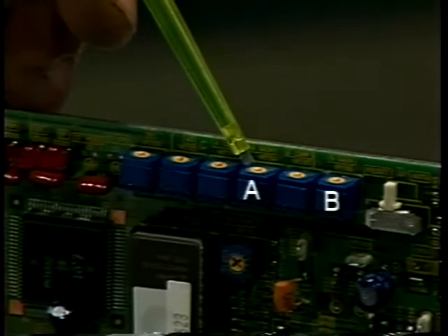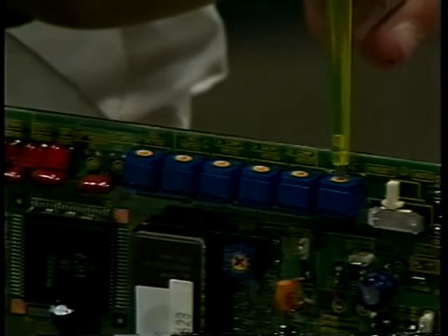Now it's time to adjust the A and B gain pots. When the gain is misadjusted, you can see fluctuations from one side of the envelope to the other as the A gain pot is turned. Do the same for the B side and adjust for a level envelope. Confirm this procedure by running the tape from forward to reverse and back again.